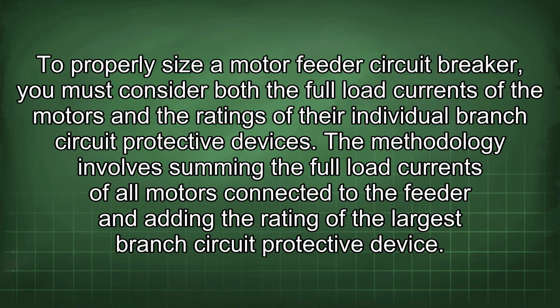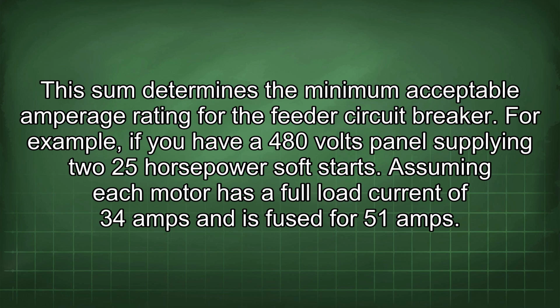To properly size a motor feeder circuit breaker, you must consider both the full load currents of the motors and the ratings of their individual branch circuit protective devices. The methodology involves summing the full load currents of all motors connected to the feeder and adding the rating of the largest branch circuit protective device. This sum determines the minimum acceptable amperage rating for the feeder circuit breaker.